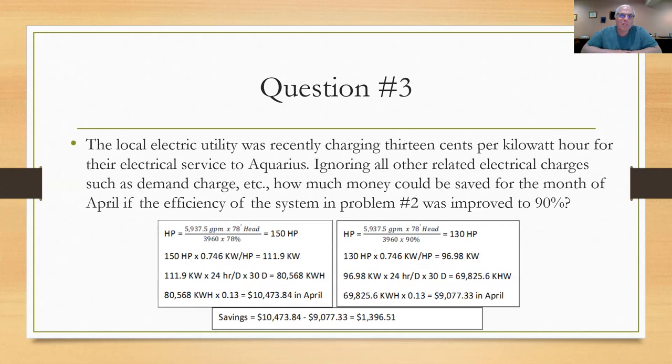On the left-hand side, I set up the equation for the 150 horsepower problem, and I multiplied that 150 horsepower by the 0.746 kilowatt hours or kilowatts per horsepower, and I come up with 111.9 kilowatts. I do that for 24 hours and 30 days, 24 hours a day for 30 days. I come up with a usage of 80,568 kilowatt hours for the month, and at 13 cents per kilowatt hour, it comes out to $10,473. Now, if I were able to run that same system under the same conditions except being 90% efficient rather than 78% efficient, I would work that through and come down with a $9,077 cost for April. So subtracting the two, I could expect to save $1,396.51. That's for the month of April at 90% efficiency. Hope you got that right. We'll move on to question number four.